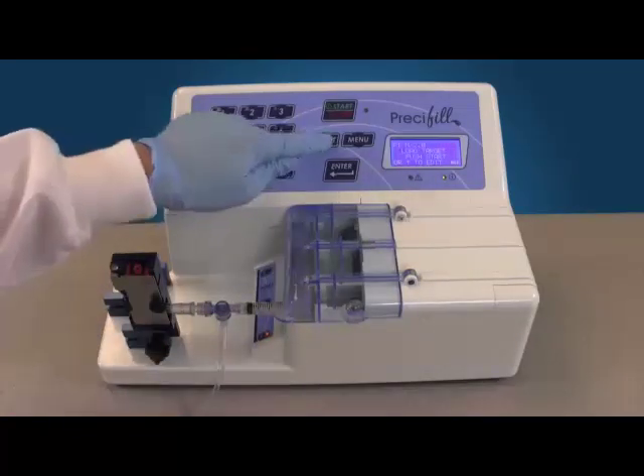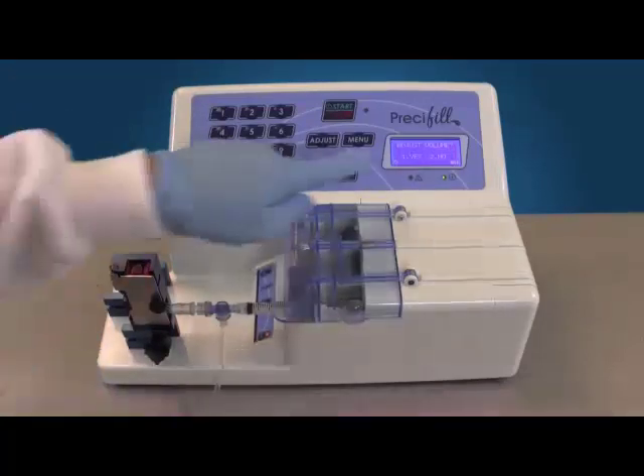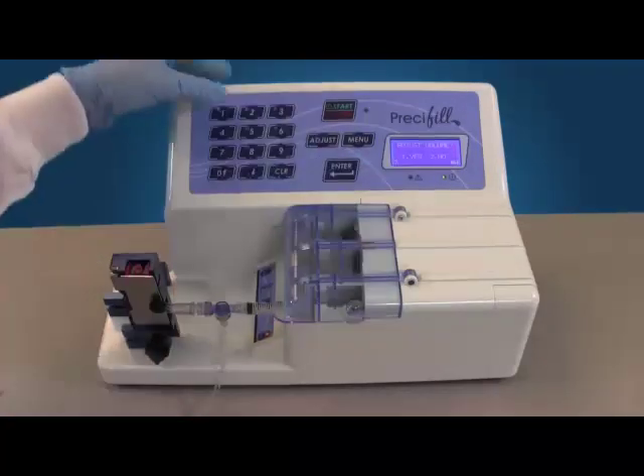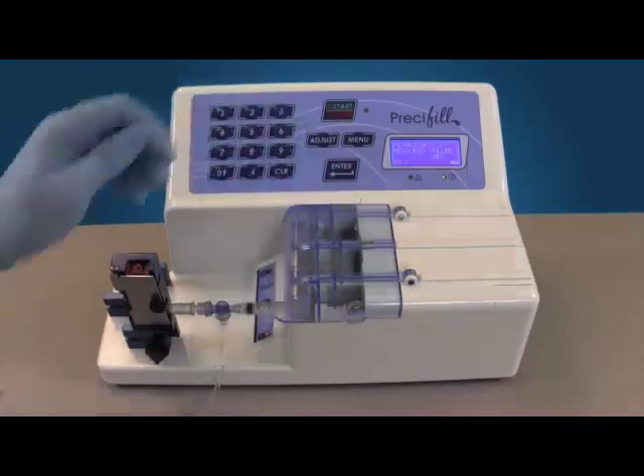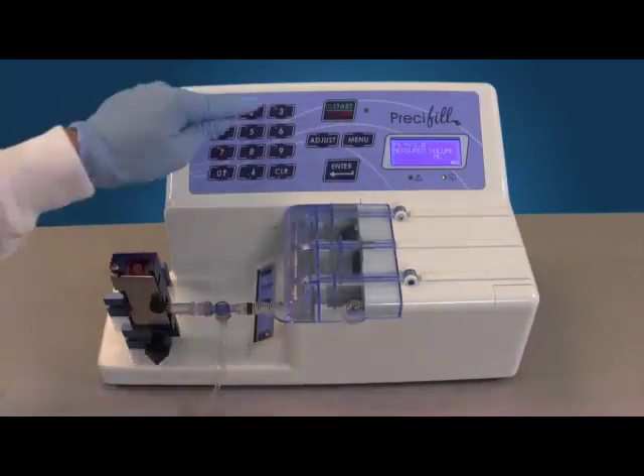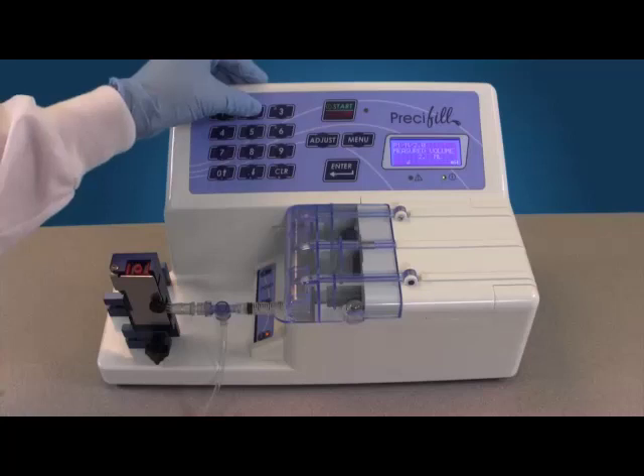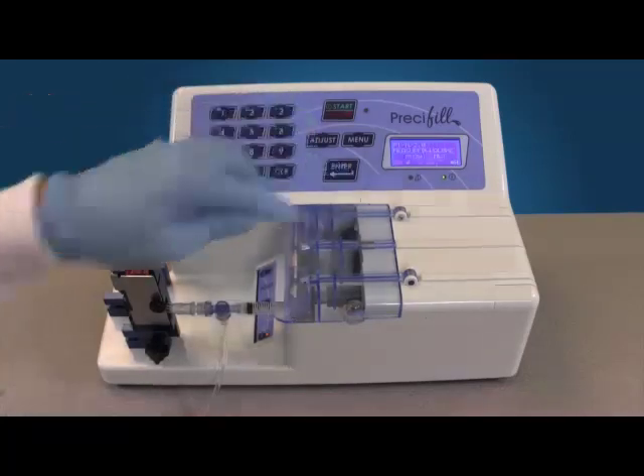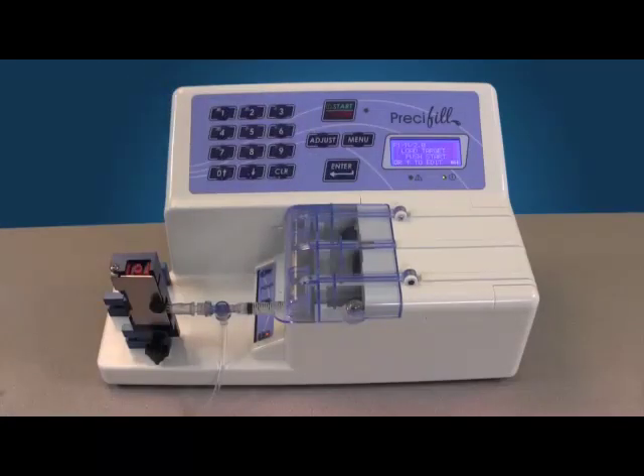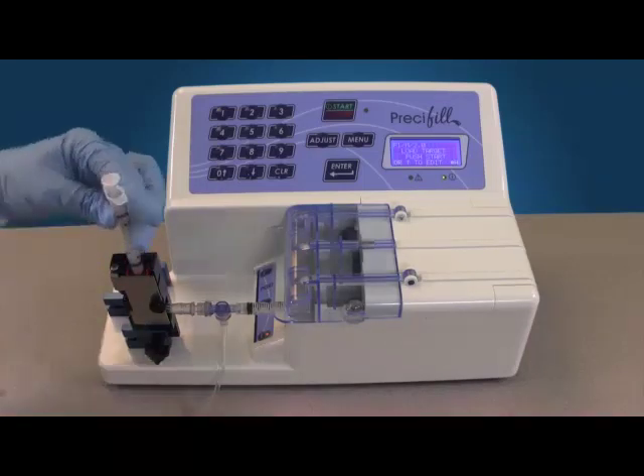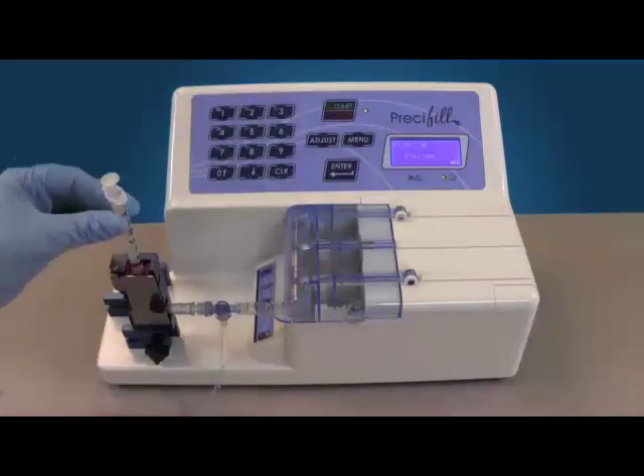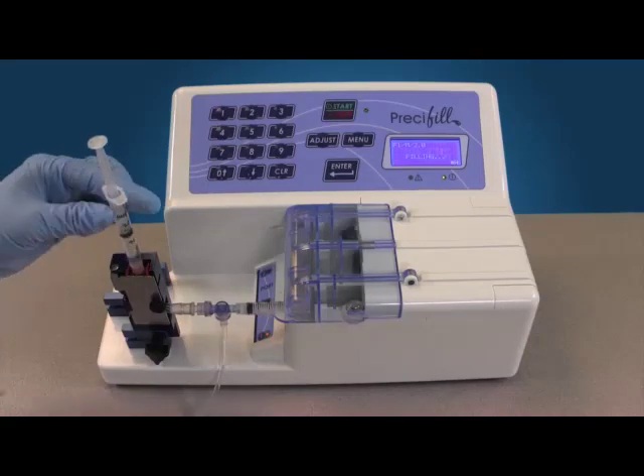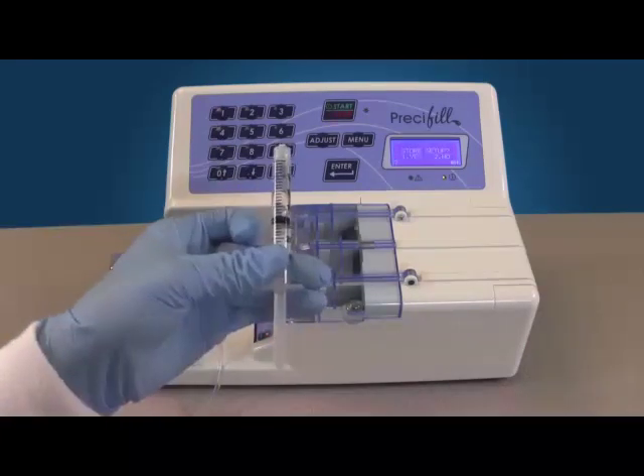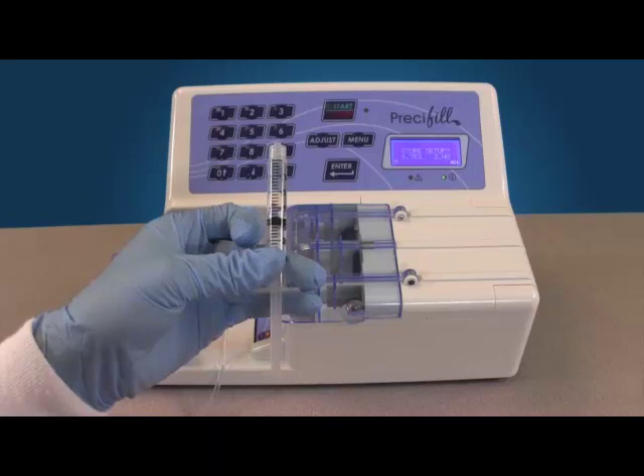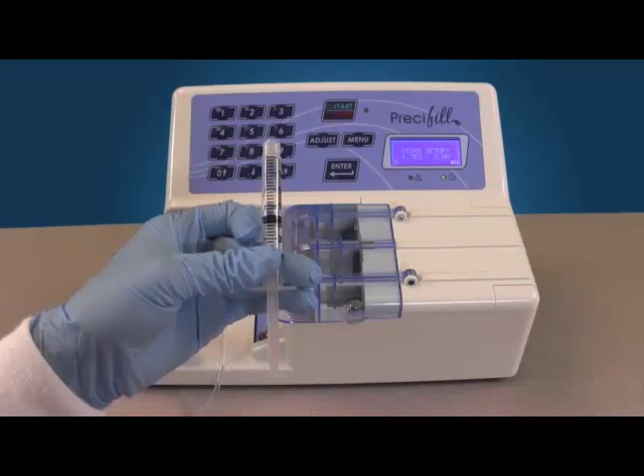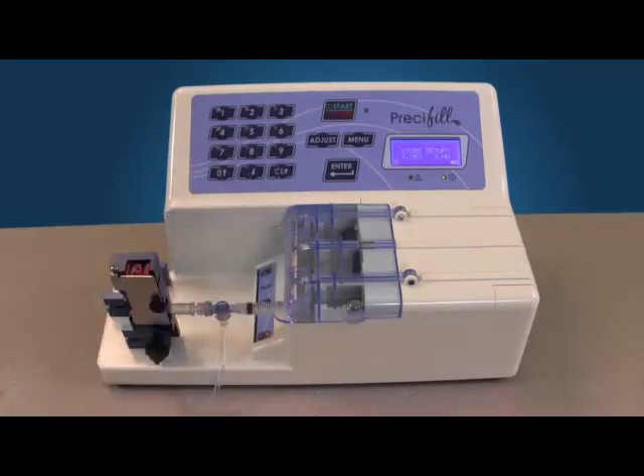To adjust, press the Adjust button. The screen reads Adjust Volume. Press 1 for yes and enter. Enter the exact measured fill volume as observed and enter. Fill an unused IV target syringe with a production dose. Confirm correct volume is achieved, or fill a new syringe and adjust calibration until correct. On average, only one adjustment is needed.